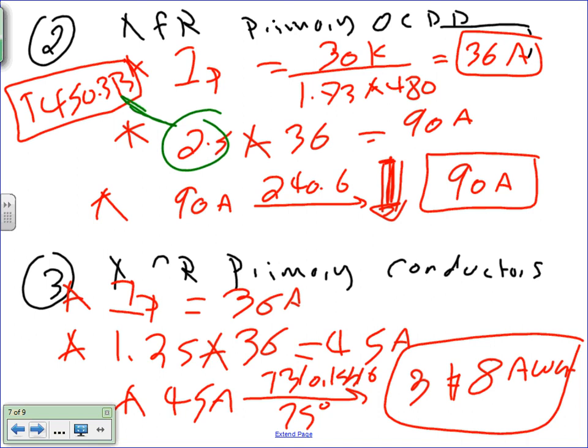Again, minimum. If you find number 6 or higher than that, not a big deal. But bare minimum, directly from 75, right? Number 8, the bare minimum. You're highly unlikely, guys, to find number 8. Probably they put number 6 or higher just because of voltage drop or whatever.